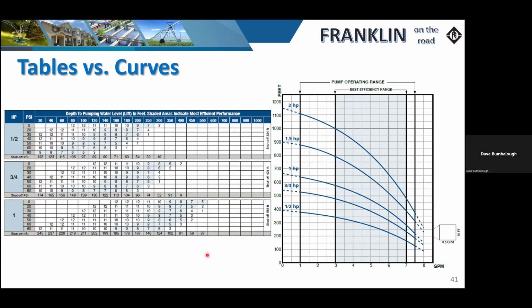Now, the other thing is, I see a lot of times contractors will use these tables. Just be wary, because these tables do not take into consideration friction loss. Okay, I always like the curves better because I can see where everything is falling on the curve. I can see how close everything is, and you can do the same thing here. If there's no numbers out there, that means don't be there. You can't be there. Typically, the grayed out area is where we want to keep your efficiency ranges. But just remember that these numbers here are from where the water level is pumping from, not where you're setting the actual pump and motor. Okay, so keep that in your mind.